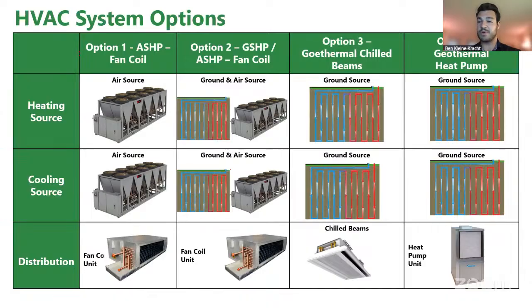In my opinion, option 4 is probably the most simple, but it does have the most distributed kind of maintenance items. This is a 2-pipe system. The only pipes in the building would be coming from the well field to each one of the heat pumps, and the heat pumps can be simultaneous. One can be heating and the next room over can be cooling, and in that situation they're sharing the load, so you're furthering your efficiency. This is a 2-pipe with single suction pumps, compared to a 4-pipe system which would have hot water pumps and cold water pumps, and 2 separate closed loop systems, when the geothermal option would only have one.